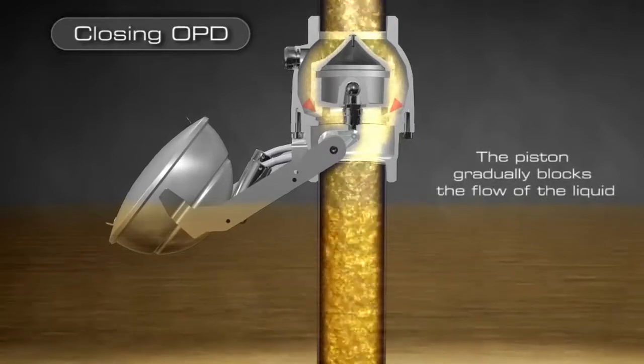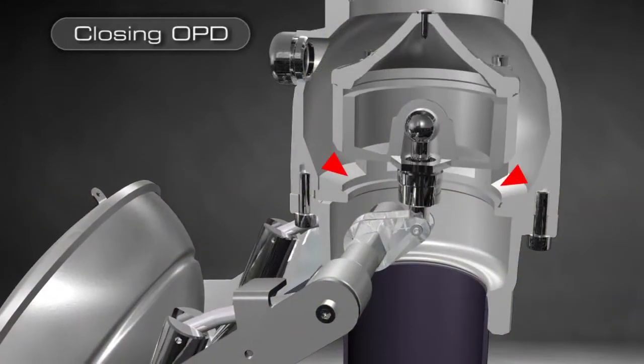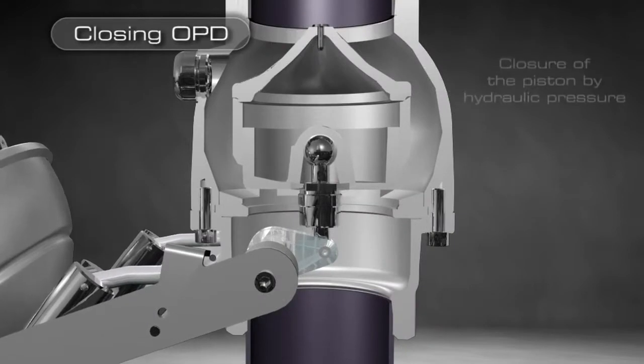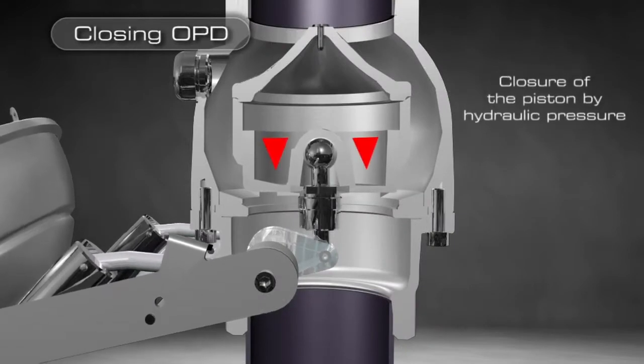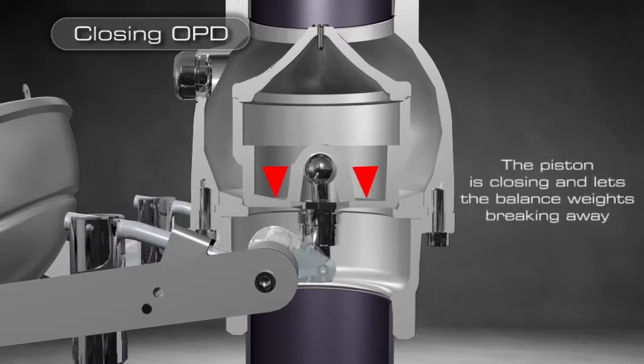As filling is taking place, the piston gradually blocks the flow of the liquid and the hydraulic pressure increases inside the stop valve. The hydraulic pressure lets the balance weights break away from the float spacer and makes the piston close.